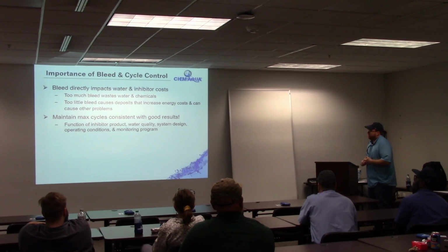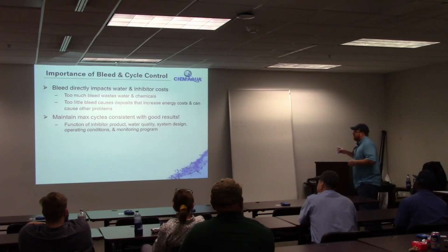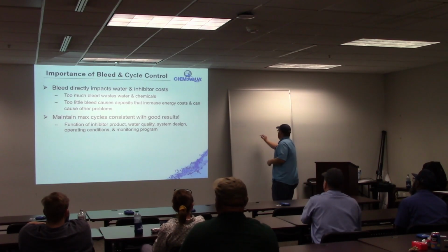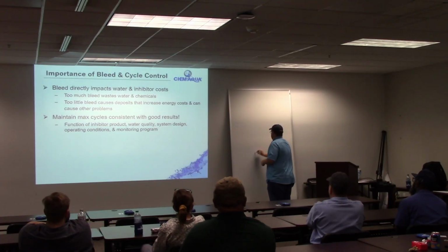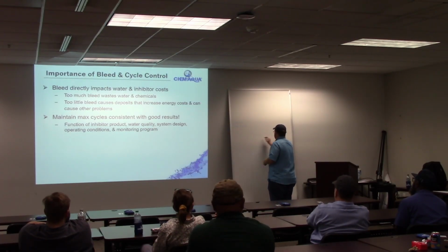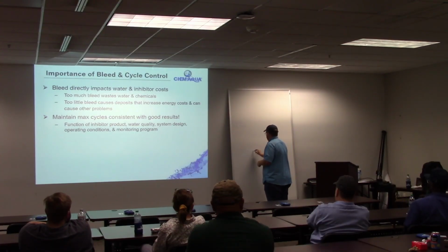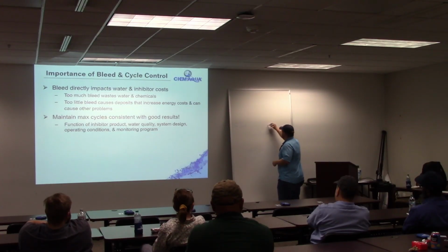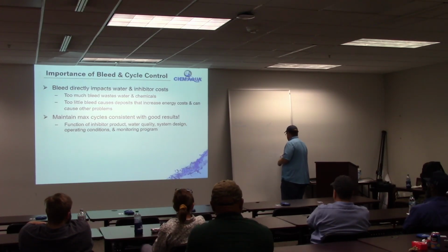So I'm going to draw a little diagram for you guys so we can talk about cycles. We're going to pretend that this is a cooling tower. This is going to be your makeup. This is evaporation. And this is going to be your blowdown, and this is your water level here in the cooling tower.